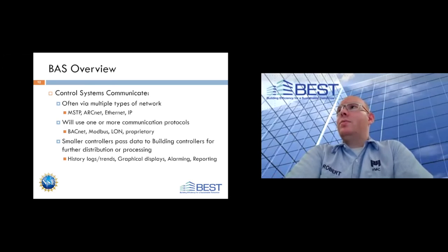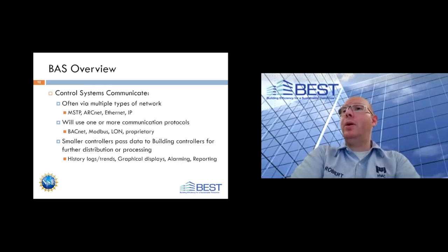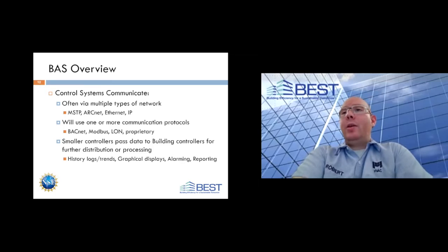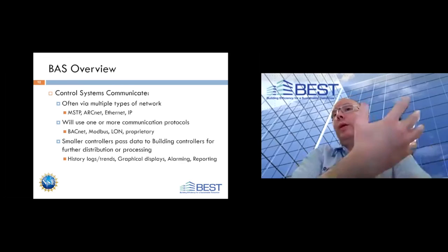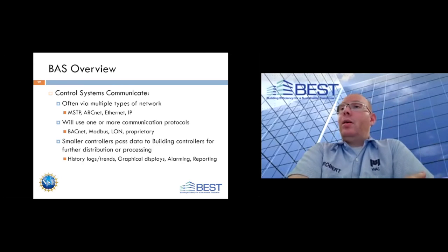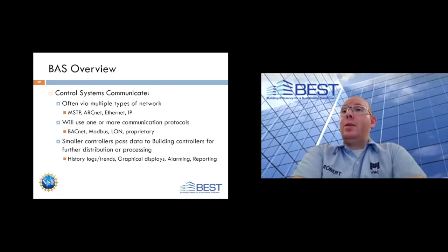ArcNet is not as popular as MSTP or any of the others. I think there are only a few companies left that support ArcNet, actually. ALC, Automated Logic, is one of them. It's kind of their backbone for communication with their plant controllers, and they implement it very, very well. Ethernet and IP-based network communications, what we think of as modern network communication, and even wireless networks are definite possibilities within a system.